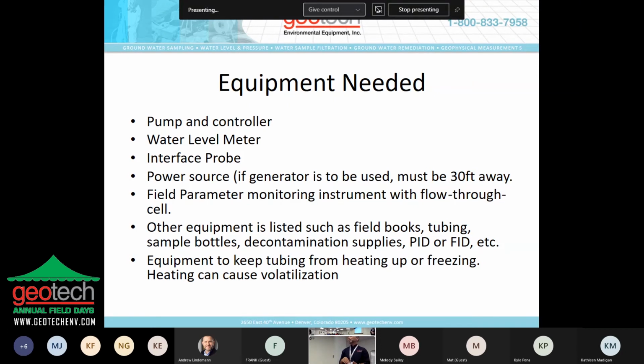And there's also certain criteria too. Your flow cell cannot be heated up or frozen, right? That changes the sample. Extreme heat and sunlight can actually volatilize your sample even with the flow cell. So you need to be as close to the well as possible. And if it's a hot sunny day, like in Arizona or here in Denver, they also recommend shading your sample flow cell, shading your sample tubing. But the same is true during the winter when we're in a freezing environment, right? We can't have our samples starting to freeze up on us and get too cold. That changes things as well. And it could also make it very hard for us to know when we've actually stabilized if temperature is changing on us, because temperature is one of our stabilization criteria.